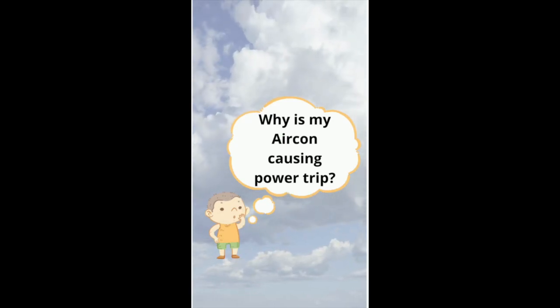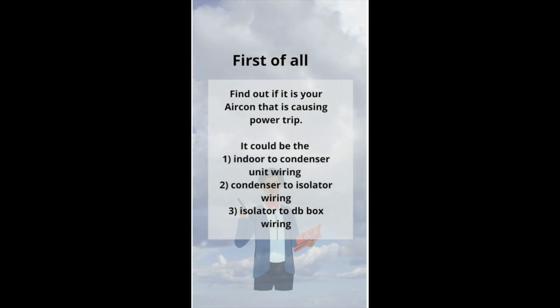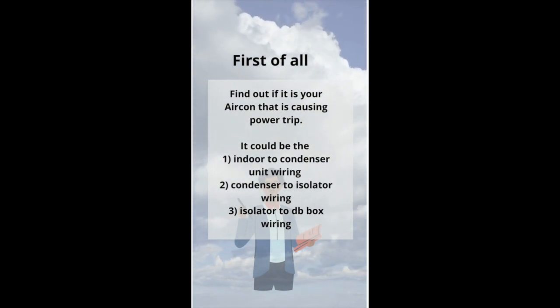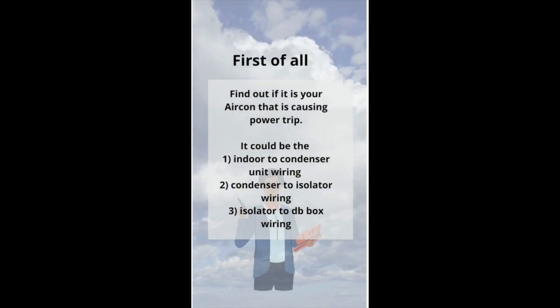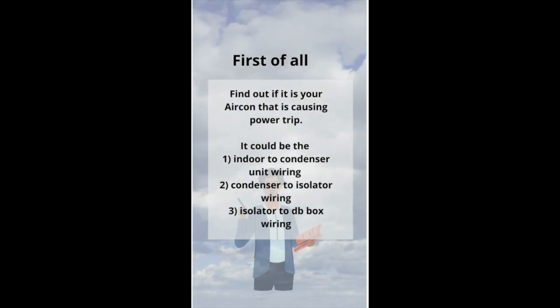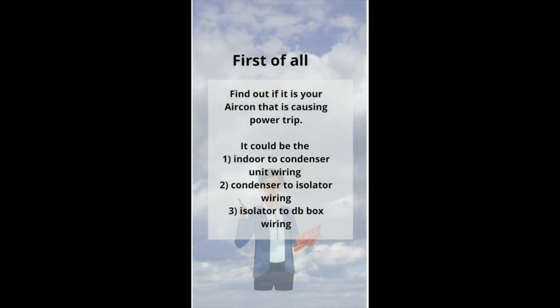Why is my aircon causing power trip? Well, first of all, you have to find out if it is your aircon that is causing the power trip. Other than your aircon and other electronics items, it could also be the indoor to condenser unit wiring, the condenser to isolator wiring, or the isolator to DB box wiring.